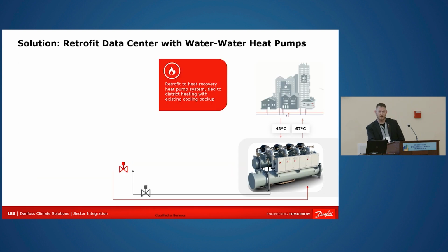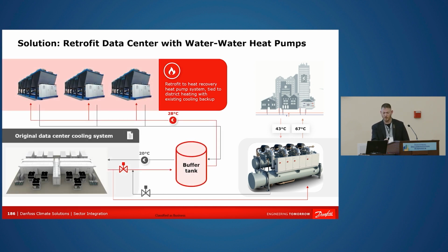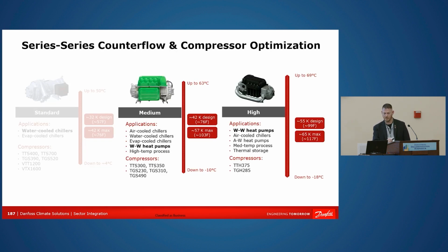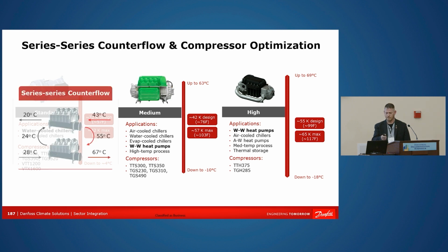So one of the solutions is we have retrofitted our data center with water heat pumps. So the original data center cooling system didn't have the heat pump, they just had a buffer tank and some other solutions involved into it. Well, we added a heat pump into it with a 43 and 67 for our things. We had a series counterflow compressor for the optimization of that system. And this is what we came up with at the end, which would give us a 43C in, down to 55C to 67C back out. And to the other side is 20C going in and 20C out.